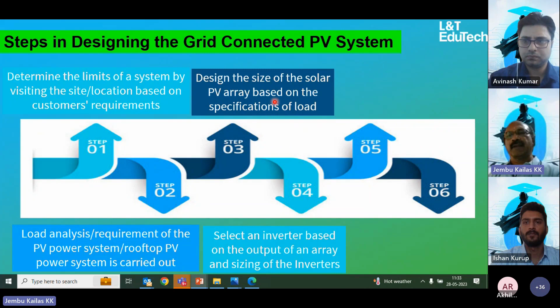Inverter sizing is based on power output, but we also need to consider inverter characteristics. You have to see what types of inverters are available in the market, find their characteristics, and match them with your power requirement. This selection can be done manually or through PV system software, since the software has data on available inverters in the market. Then sizing the battery is another important thing.